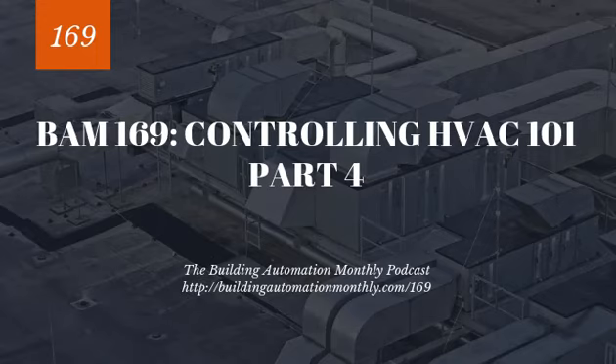Now with steam, last thing I kind of want to leave you with here is the two strategies for 1/3 and 2/3 control and what condensate is. So with 1/3 and 2/3 control, you have the scaling strategy, right? You implement a single process loop, and this single process loop then has scalar objects. We're talking about the programmatic side, right? So actually inside the controller programming. So you have a single PID loop that drives off of whatever temperature you're driving off of, typically discharge air. And then you go and you drive your 1/3, 2/3 valves scaled off of this.